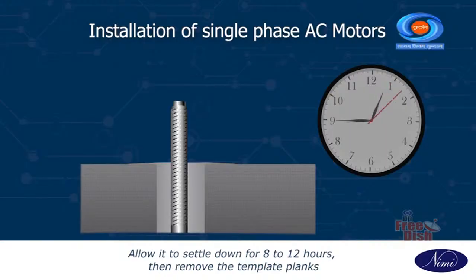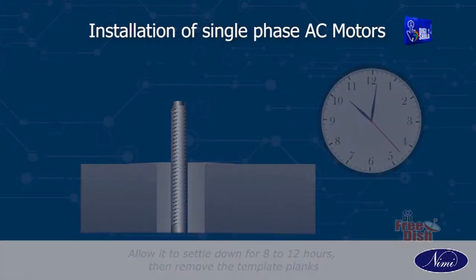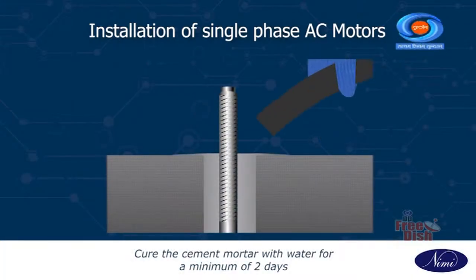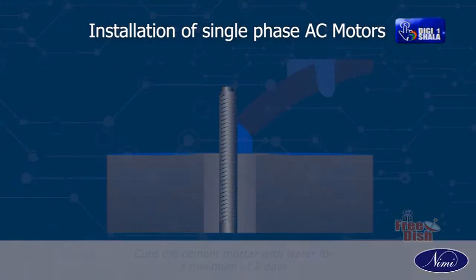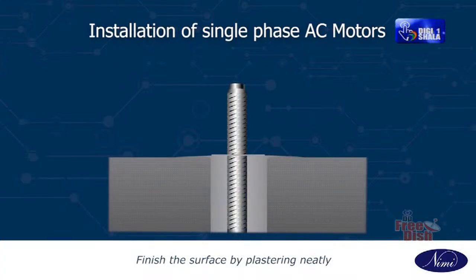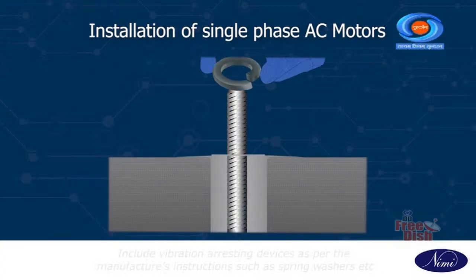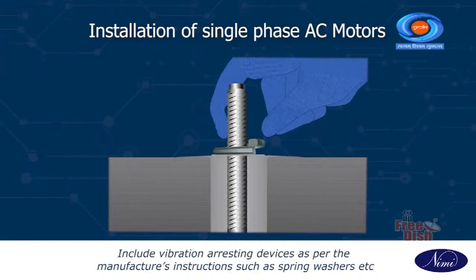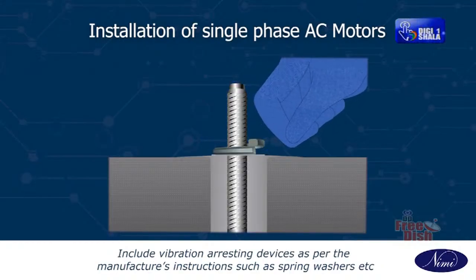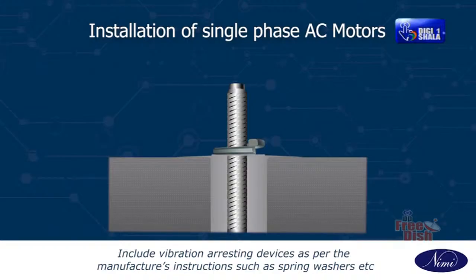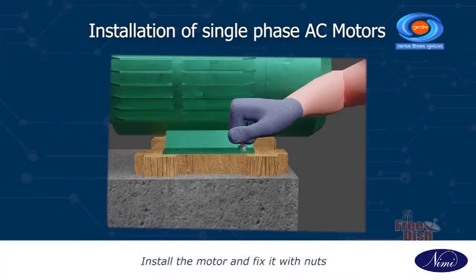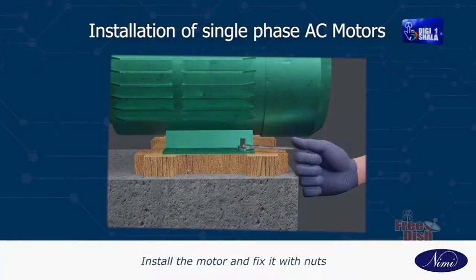D. Allow it to settle down for 8 to 12 hours, then remove the template planks. E. Cure the cement mortar with water for a minimum of 2 days. F. Finish the surface by plastering neatly. Include vibration arresting devices as per the manufacturer's instructions, such as spring washers, etc. Install the motor and fix it with nuts.